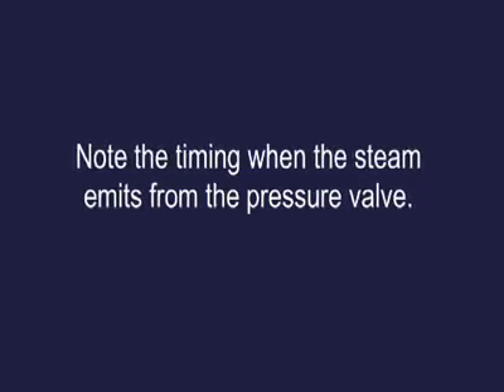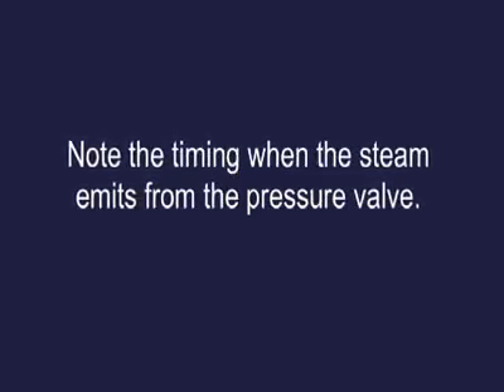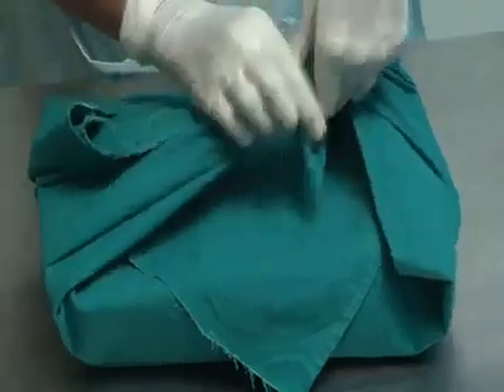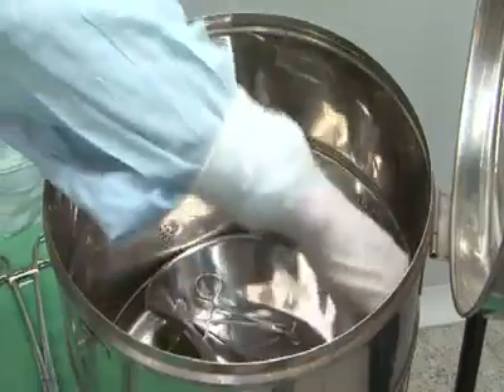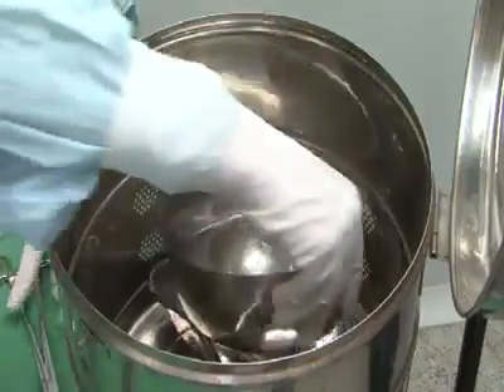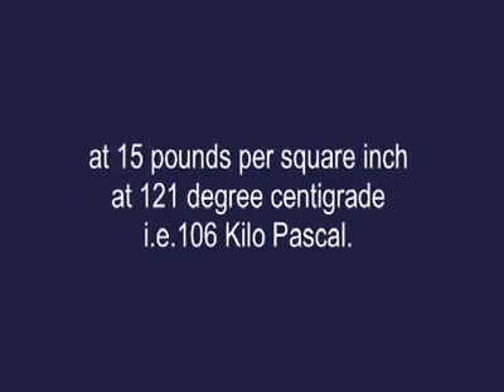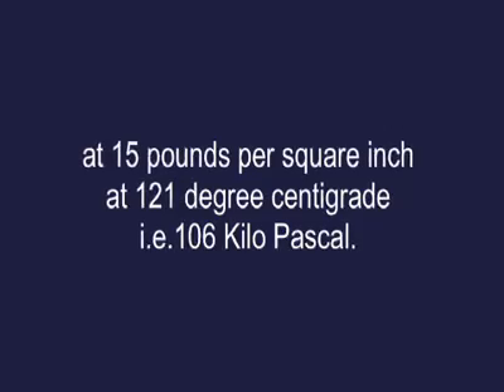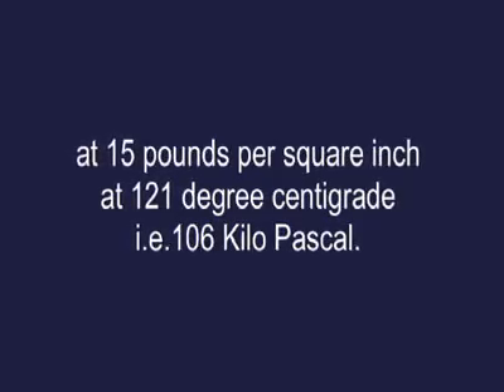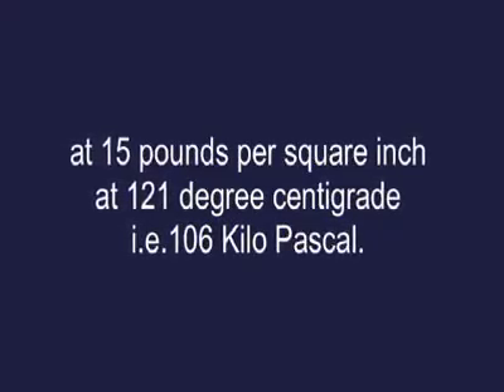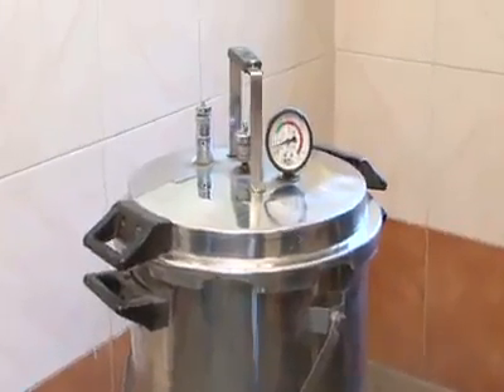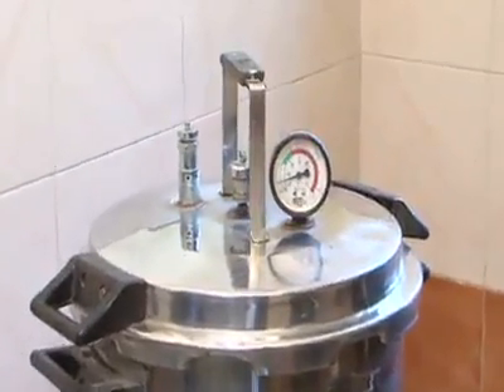Note the timing when the steam emits from the pressure valve. Keep the wrapped items for 30 minutes and unwrapped items for 20 minutes at 15 pounds per square inch at 121 degrees centigrade, that is 106 kilopascal. Allow autoclave to cool for 30 minutes before opening.